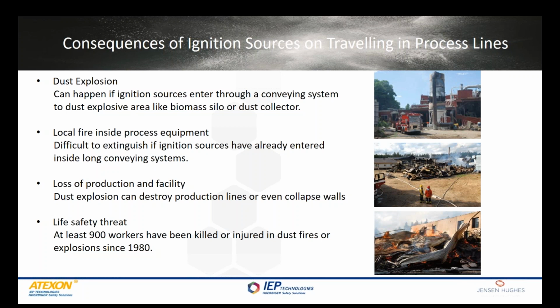It is not always dust explosion that can happen, but many times just local fire in certain area of the production line. And even smaller local fires cause many times relatively long production stops. And last but not least, life safety threat is something that can never be underestimated. At least 900 workers have been killed or injured in dust fires or explosions since 1980.